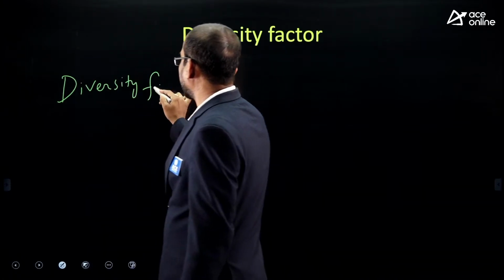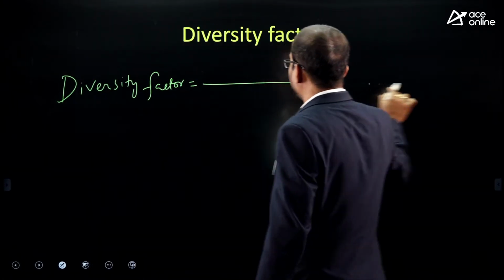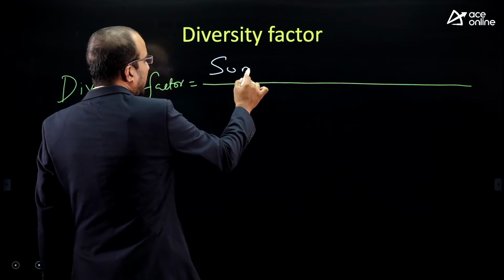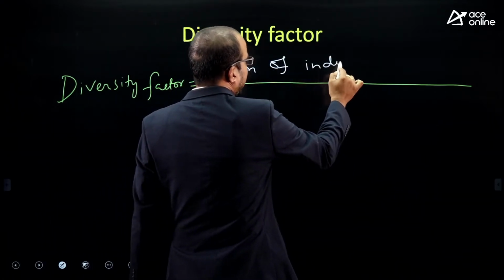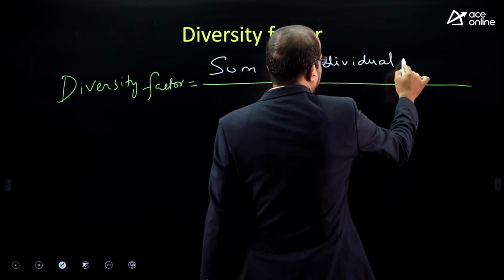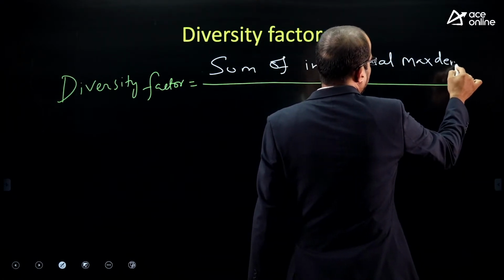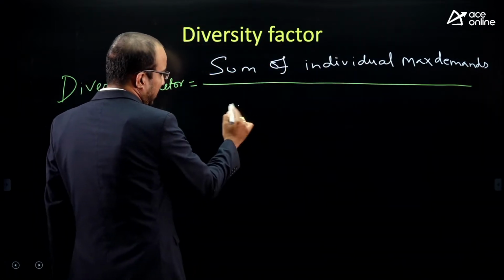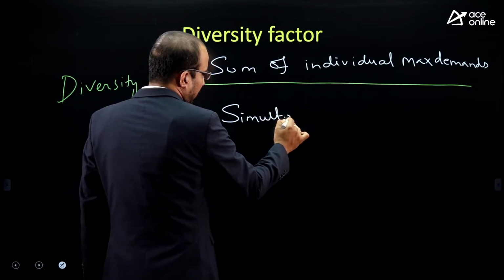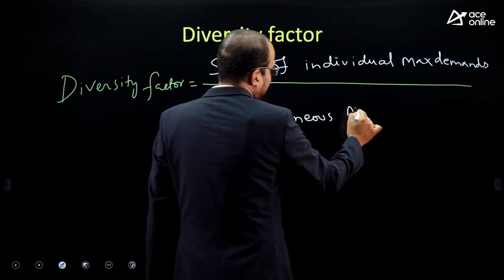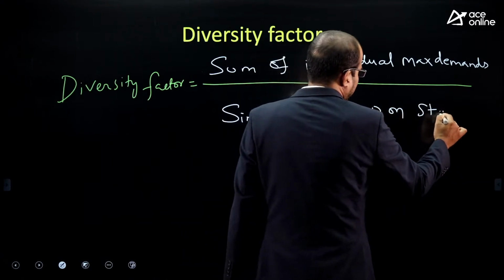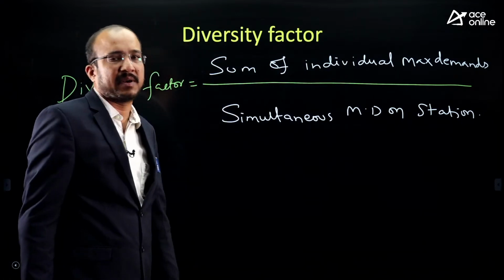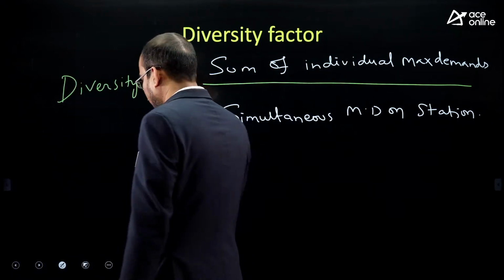Diversity factor is the ratio of the sum of individual maximum demands to the simultaneous maximum demand on the station.